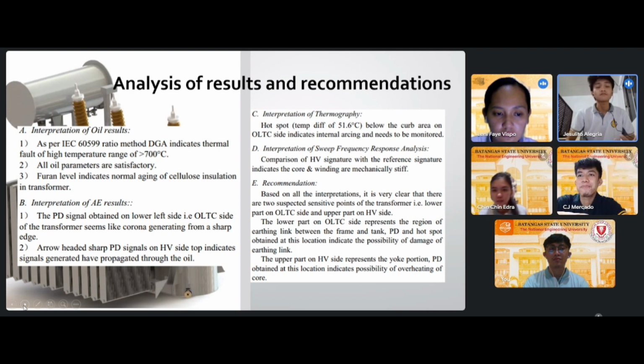Second interpretation, the acoustic emission results. First, the PD signal obtained on the lower left side, the OLTC side of the transformer, seems like corona. The arrow-headed sharp PD signals on the high voltage side top indicate signals generated have propagated through the oil.